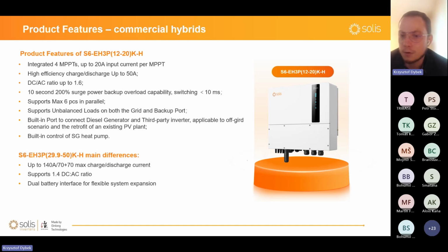Supports unbalanced load on both the grid and backup port. And this is also what is different here, especially when you have battery. You not necessarily want to use balanced load during discharge. Smart, lightweight, intelligent, and easy for installation and commissioning. And built-in port to connect diesel generator or a third-party inverter. This is applicable for off-grid scenario and the retrofit of an existing PV plant.